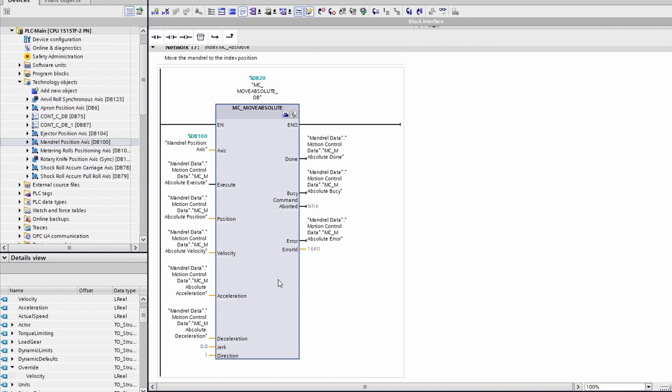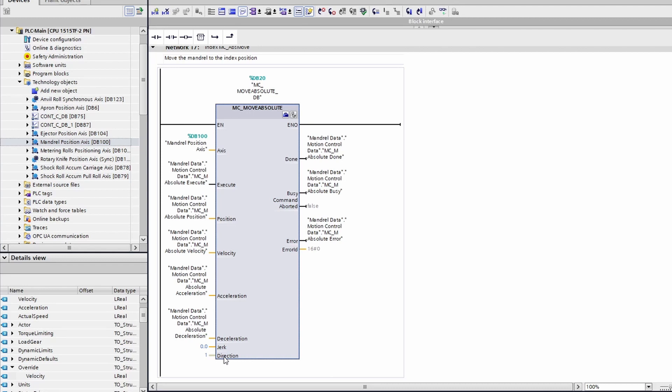With that said, let's take a look at this direction bit on the input on this function. It is set up as a one, that means that this axis will always try to move in the negative direction to reach the absolute position. If you want to move it always in the positive direction, you set this to zero. If you want the axis to move the shortest distance to that position, you would put a three here.